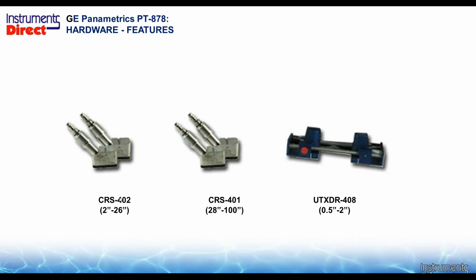The 402 is the current design with a metal case transducer. If you have the old plastic transducers, and you have the opportunity when you're upgrading equipment, I suggest you go to this design. It works much better than the old plastic transducers. The beam is more focused and the numbers are less fuzzy. A bad decision is to take your new PT878 and use the old sensors from the PT868, with the plastic and the red and all the different transducers. So you're taking old and new and marrying them together. If you've got a PT878, use the current design transducers for your optimum performance.